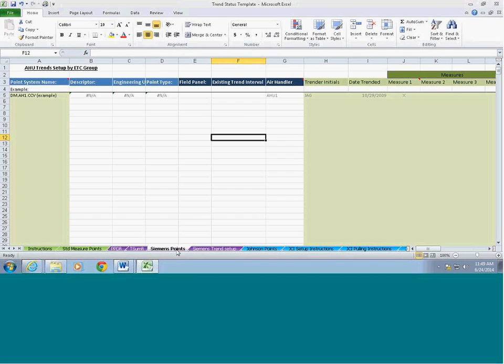One is I'd recommend starting from the top and working backward. If you get to your end goal, if you get a trend in SkySpark, you don't need to look anywhere else. It's doing what it needs to do. If you start at the bottom and check that the trend was set up and assigned to a report, you still don't know that it's making its way to the end. So you have to go through every step to verify that it's working correctly. So over at the top, the end goal is SkySpark. That's the first place I'd look to see whether or not we got the trend that we asked for.